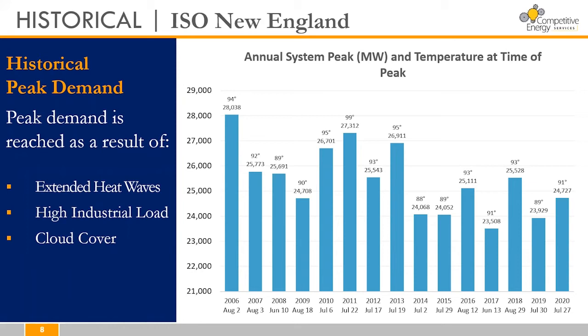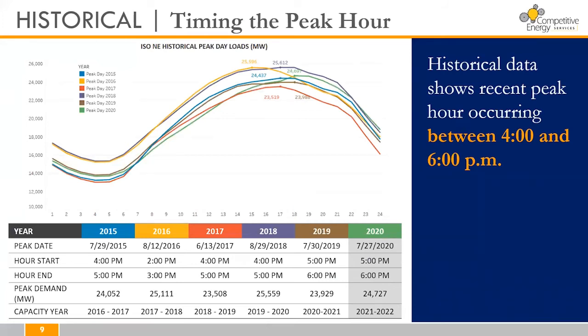You can see that the system peak for each year dating back to 2006 occurred between June and August on a day when temperatures rose into or above the high 80s. Over the past five years, peak system demand has been roughly between 23,000 and 26,000 megawatts. If our goal is to reduce electricity demand on the peak day, we want to focus our curtailment efforts on the peak hour — the specific hour when grid demand is at its highest — which is the hour used to determine your capacity tag and later your capacity costs. This graph shows a daily demand curve over the past six years, with the peak hour for each summer since 2017 occurring between 4 and 6 pm.